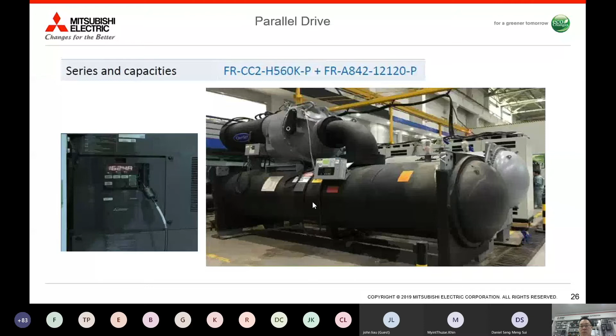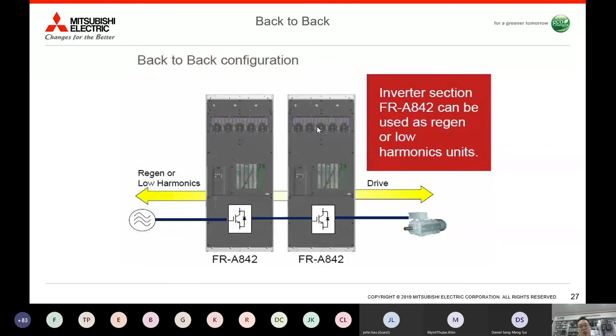The A series can be used as a regenerative PWM converter with an internal option unit. Another purpose of using this back-to-back configuration is as a low harmonic unit. At the inverter input, we want compliance to THDI, the total harmonic current distortion, to be 5%. So in this configuration there are two main purposes: one for regen, one for low harmonic.